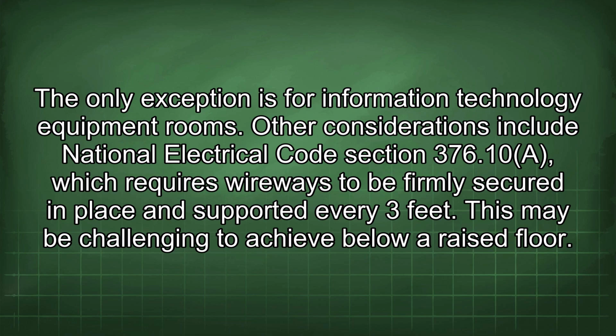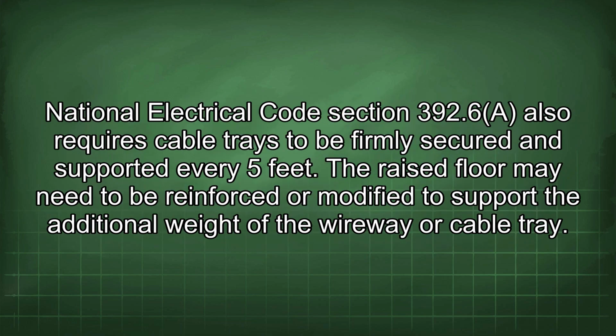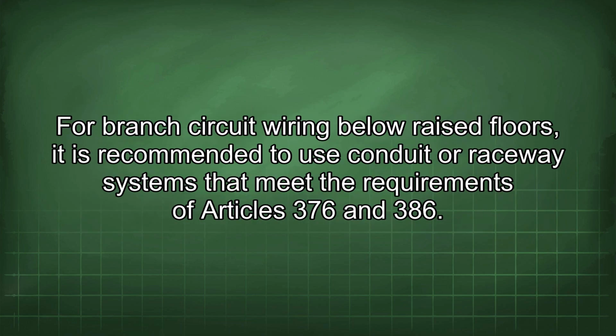Other considerations include National Electrical Code Section 376.10(A), which requires wireways to be firmly secured in place and supported every 3 feet. This may be challenging to achieve below a raised floor. National Electrical Code Section 392.6 also requires cable trays to be firmly secured and supported every 5 feet. The raised floor may need to be reinforced or modified to support the additional weight of the wireway or cable tray. For branch circuit wiring below raised floors, it is recommended to use conduit or raceway systems that meet the requirements of Articles 376 and 386.